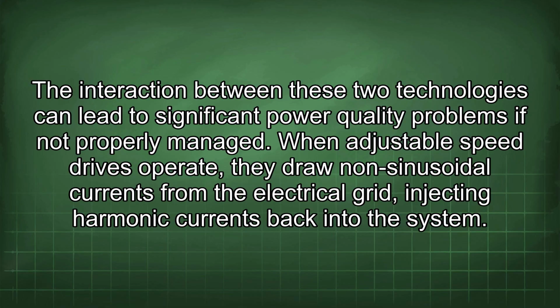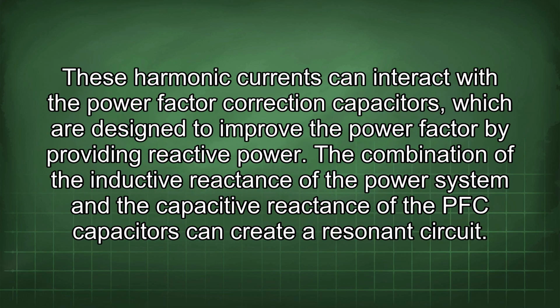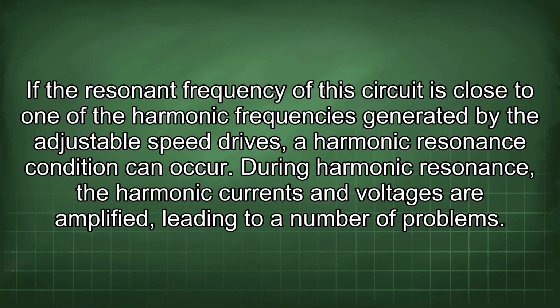When adjustable speed drives operate, they draw non-sinusoidal currents from the electrical grid, injecting harmonic currents back into the system. These harmonic currents can interact with the power factor correction capacitors, which are designed to improve the power factor by providing reactive power. The combination of the inductive reactance of the power system and the capacitive reactance of the PFC capacitors can create a resonance circuit. If the resonant frequency of the circuit is close to one of the harmonic frequencies generated by the adjustable speed drives, a harmonic resonance condition can occur.